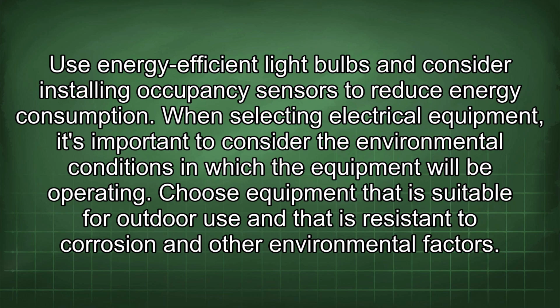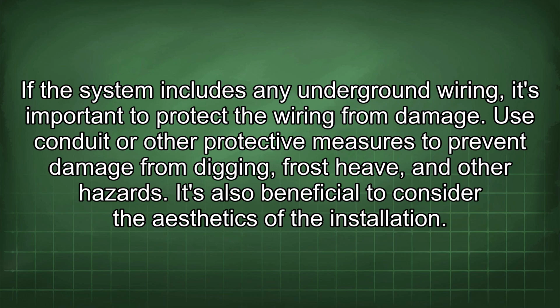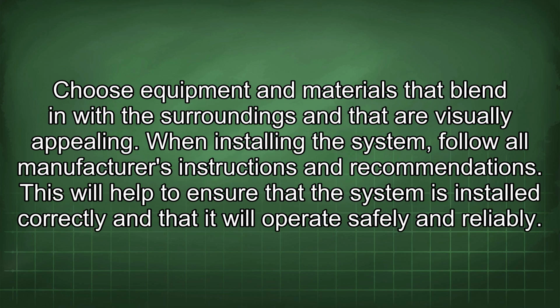When selecting electrical equipment, it's important to consider the environmental conditions in which the equipment will be operating. Choose equipment that is suitable for outdoor use and that is resistant to corrosion and other environmental factors. If the system includes any underground wiring, it's important to protect the wiring from damage. Use conduit or other protective measures to prevent damage from digging, frost heave, and other hazards. It's also beneficial to consider the aesthetics of the installation. Choose equipment and materials that blend in with the surroundings and that are visually appealing. When installing the system, follow all manufacturers' instructions and recommendations. This will help to ensure that the system is installed correctly and that it will operate safely and reliably.